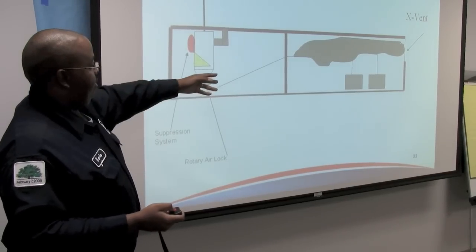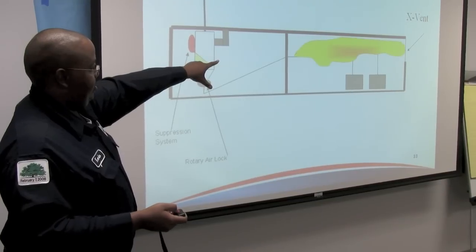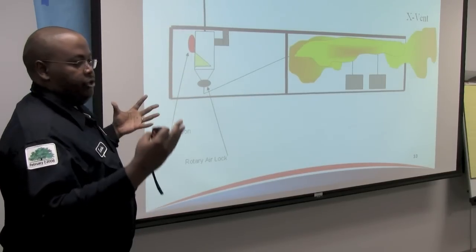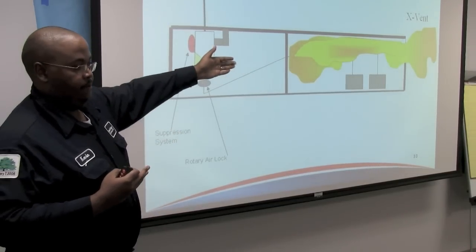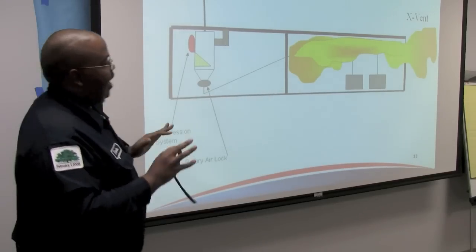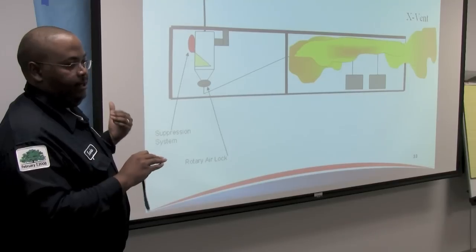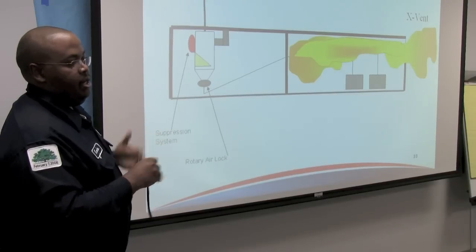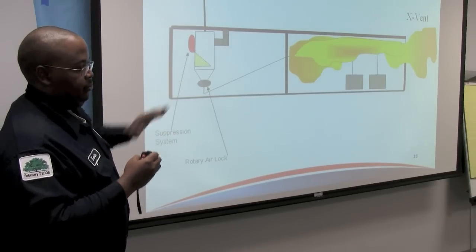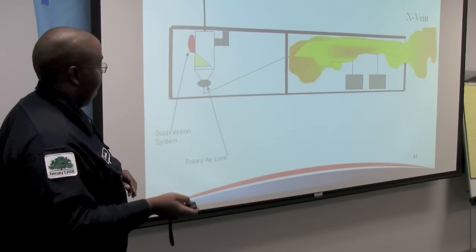Another explosion or deflagration ignites that layer of dust, and you have a larger-scale explosion that is now vented. These are the design features to consider: in the first scenario with no venting and nothing to relieve pressure, you have catastrophic loss. Whereas with proper design, you're venting in the event of an explosion to minimize that loss.